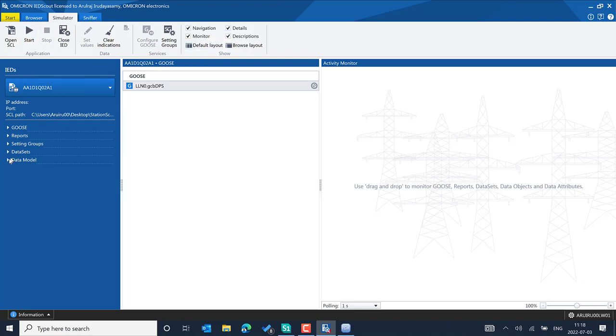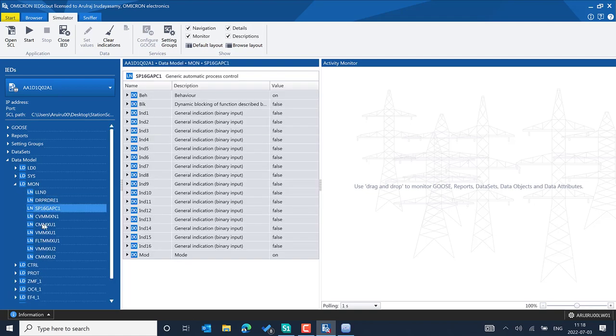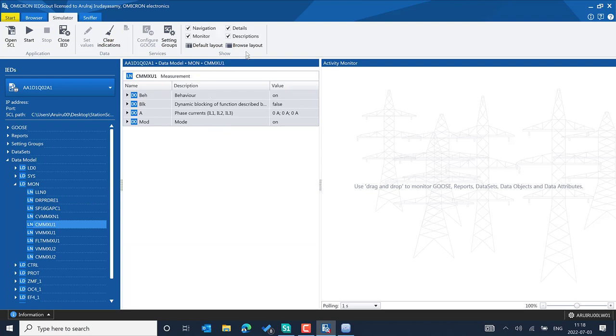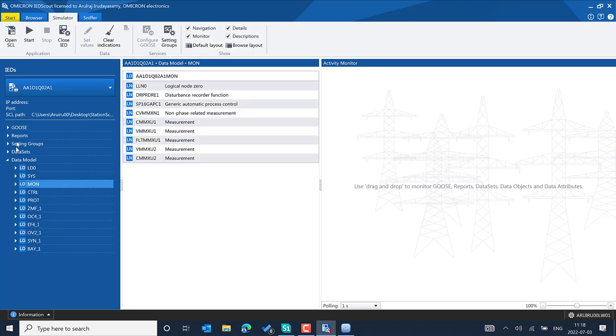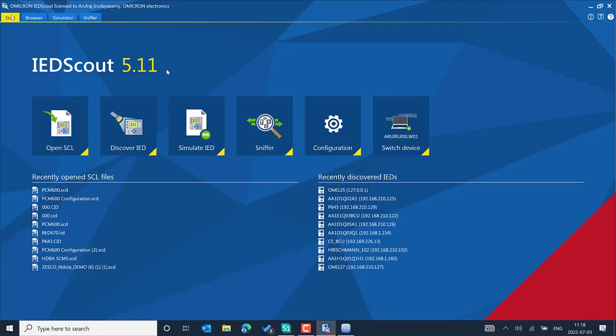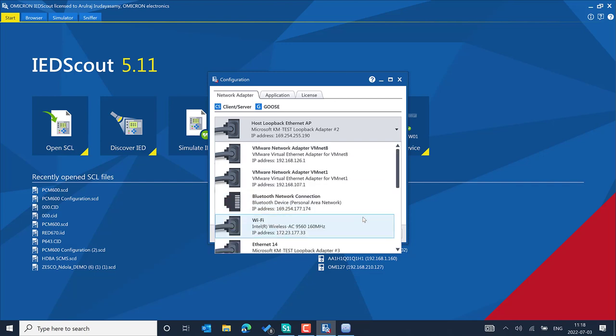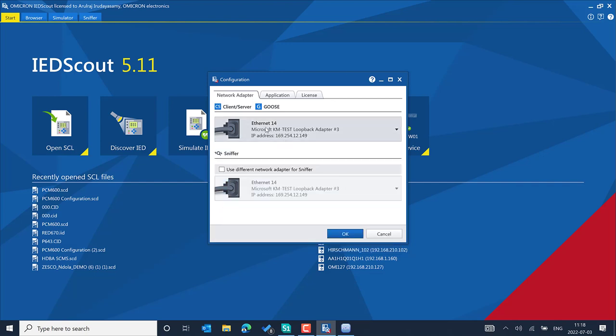As always, when working with IED Scout, enabling the description helps a lot when working with any logical node to simulate specific data attributes and change values — you get the right value description when simulating. Before you start simulating, pick the right adapter. Go to the configuration section and select the new adapter we added — for example, adapter number 3, the KM-TEST Loopback Adapter.